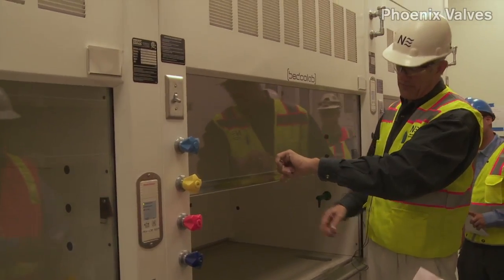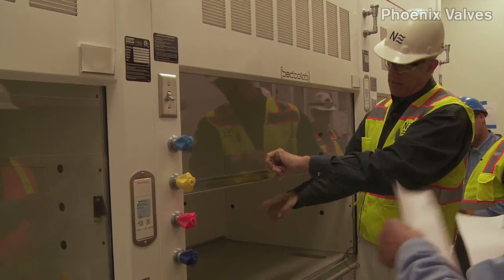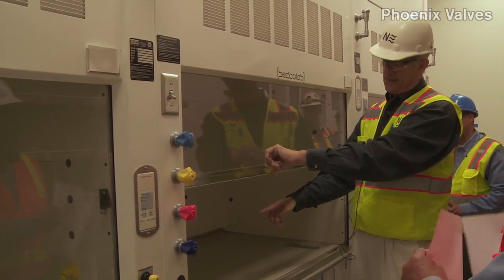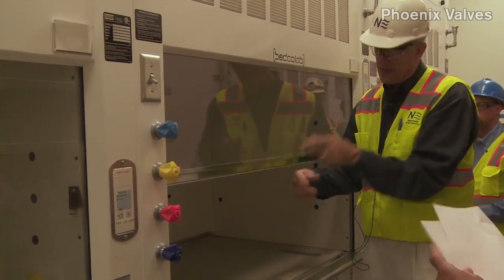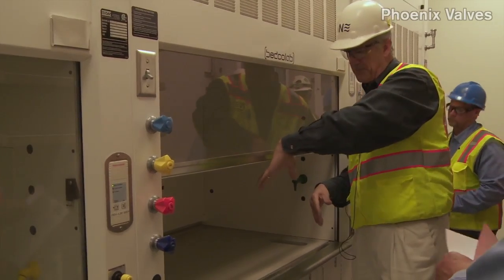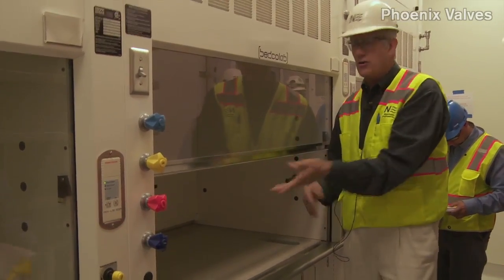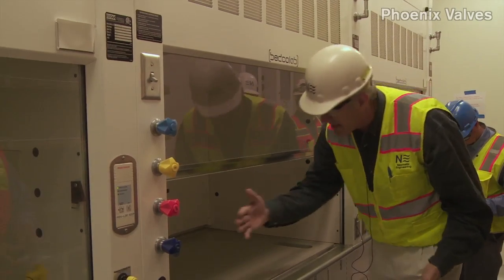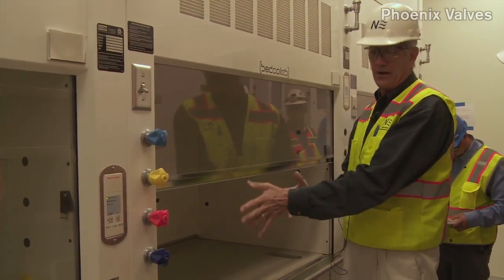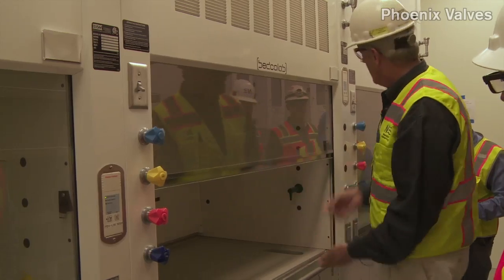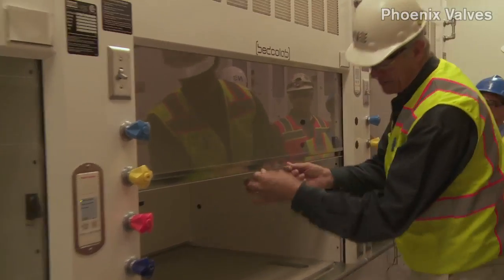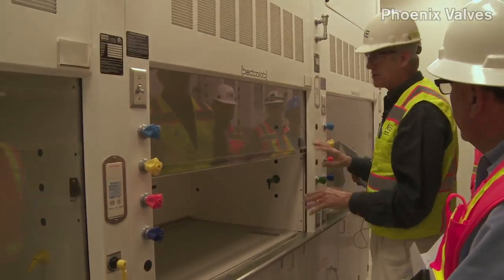If you hold it up to the sash like this, it should go in at about a 40-degree angle. So paper's too stiff. Okay. The Kim wipe tissues are a little floppy. They go in at about 40 degrees. You can't feel 100 feet per minute. So you get your finger wet. The proper capture velocity you can't feel here. But you got a green light. You can put your tissue in. You can say, good, it's flowing. It's doing what it should be doing.